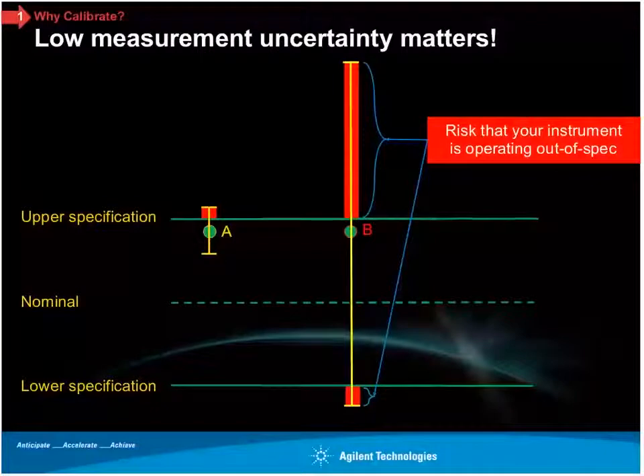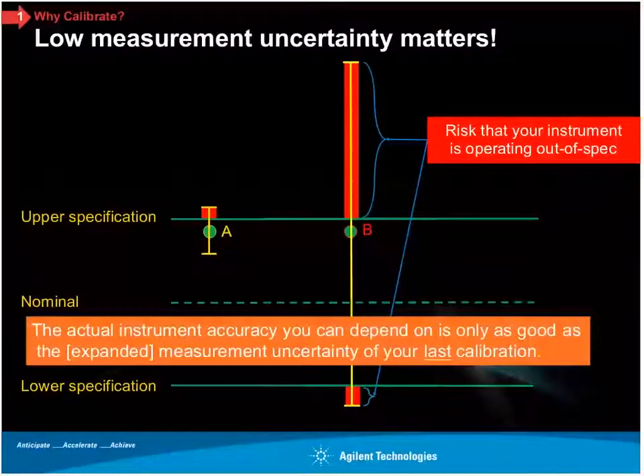So as you may know, as an OEM, we test extremely thoroughly whenever we build and first ship an instrument. And then even our very best instruments do drift over time. So it is important periodically to make sure that they're still performing according to the warranted specifications. And I'm going to show you an example in a little bit, where you can get an idea from a traceability report that the situation could actually be as bad as A versus B. And obviously, if you had a situation where the uncertainty was as large as it is with B, then the truth is it's really pure luck if you measure the instrument inside the specification. And so that's obviously a very important topic.